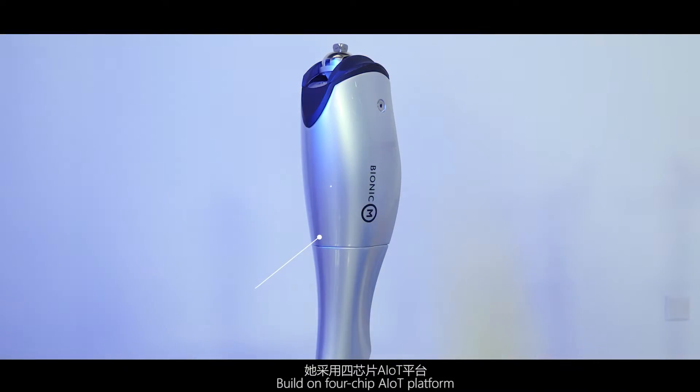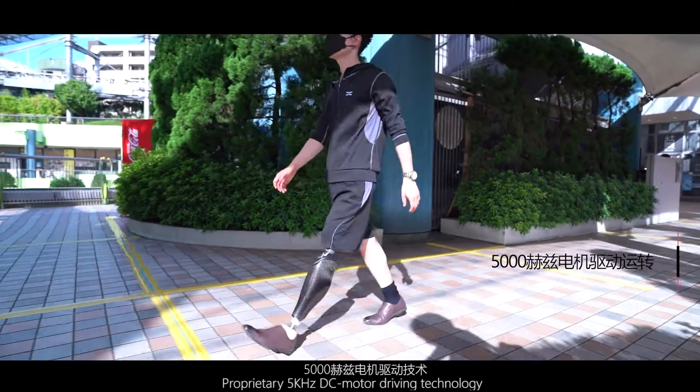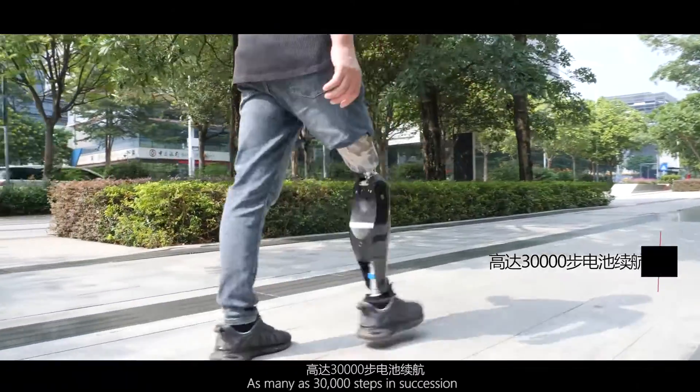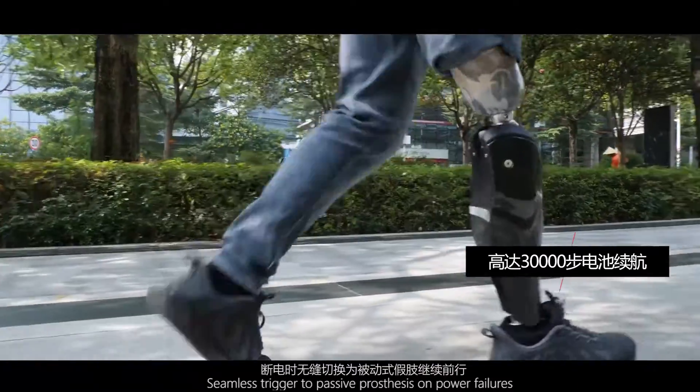Built on a four-chip AIoT platform with an advanced mechatronic system and multiple sensors. Featuring proprietary 5,000 Hz DC motor driving technology, supporting as many as 30,000 steps in succession, with seamless trigger to passive prosthesis on power failure.